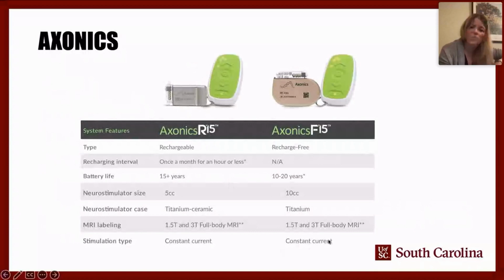Both these devices are constant current, which is, at this point, all of the devices are constant current. The idea behind constant current is that the stimulation is constantly adjusted, so that if you have impedances building up, and impedance can be scar tissue between the nerve and the device, or fragmentation in the lead itself, that constant current can adjust for that constantly without having to change how much power is going into the device. So that's why that was incorporated into this newest technology, constant current, and that was new to market with Axonics.